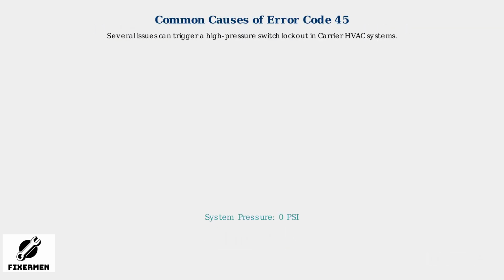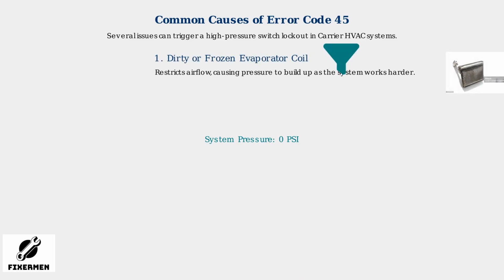Several issues can trigger a high-pressure switch lockout in Carrier HVAC systems. The system pressure rises dangerously when airflow is restricted or components fail to function properly. The first common cause is a dirty or frozen evaporator coil. When the coil becomes clogged with dirt or frost, it restricts airflow through the system. This forces the compressor to work harder, rapidly increasing the pressure in the refrigerant lines.